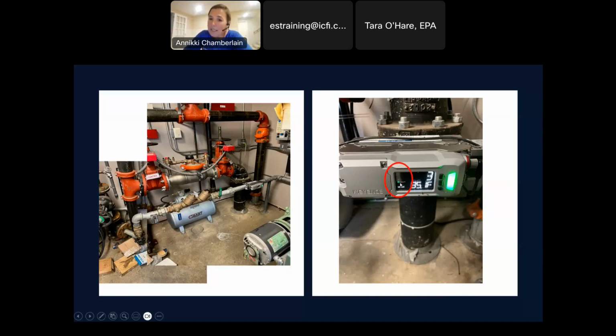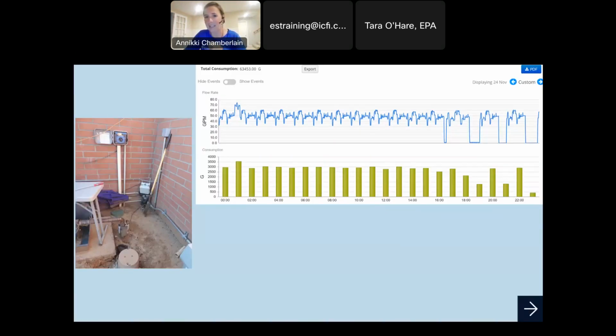So on here, we can see that my stability is really low, and that's because it's not a full pipe, right? It's just barely leaking water through. So I didn't necessarily need the volume here. I just needed to know that there was any water running at all to know that there was a failure. So not perfect, the water use may not be accurate, but it was enough to let me know I had a problem in this case.